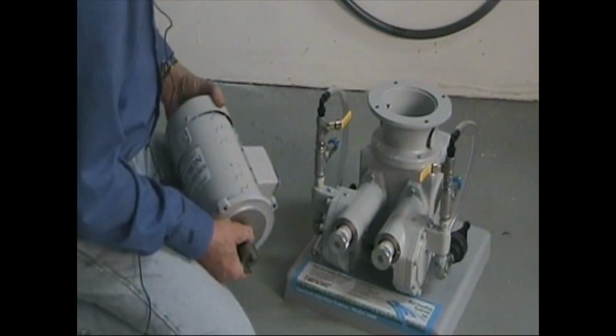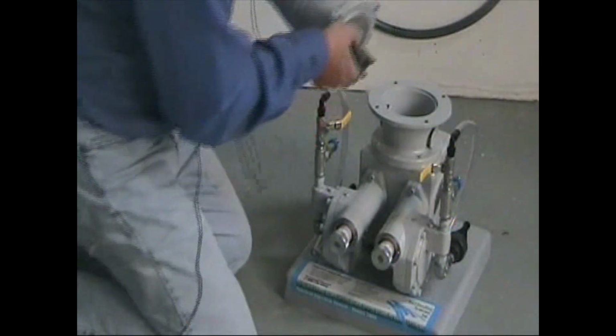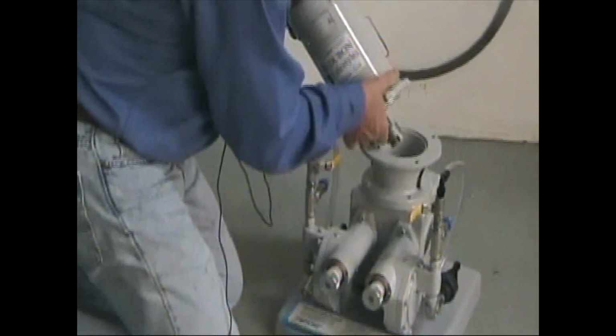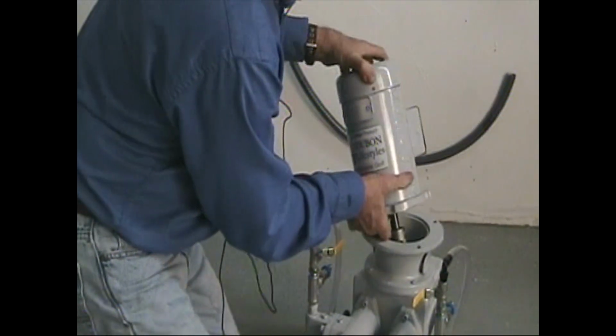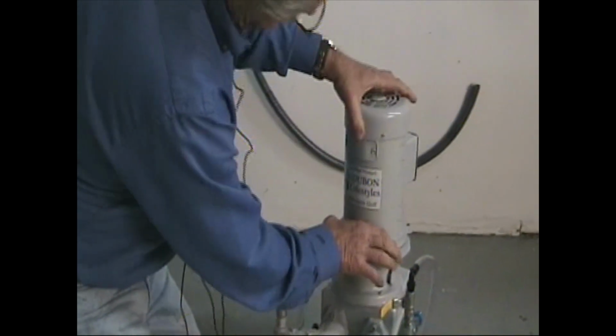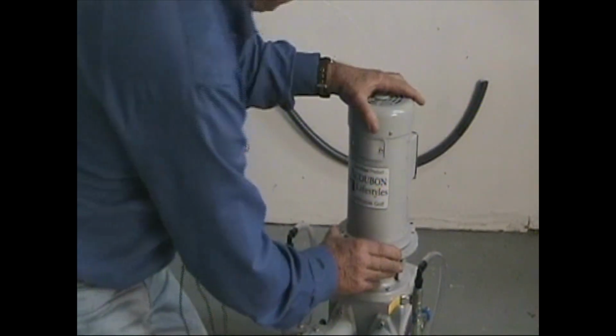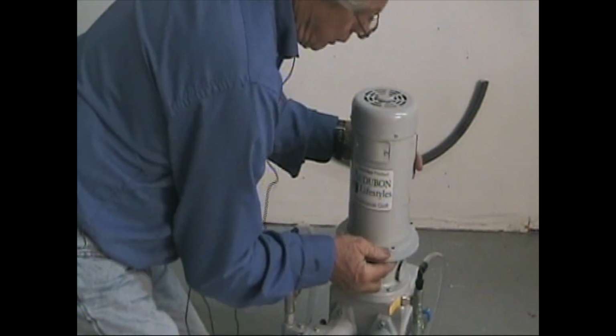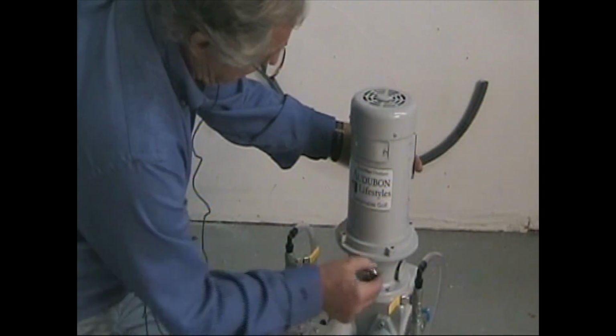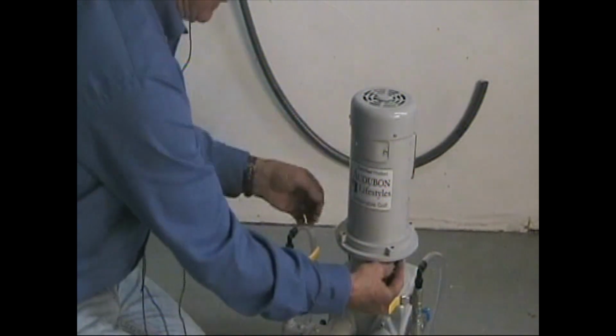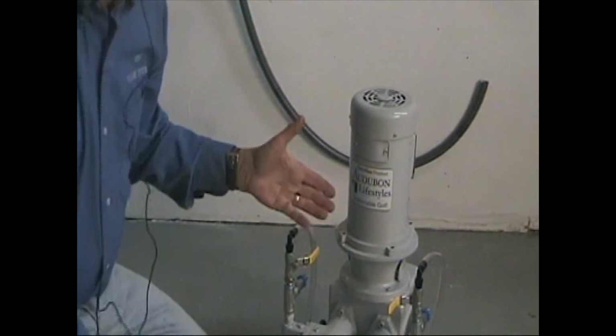Okay. The next thing you're going to do is mount the motor on the pump. The motor has a spider coupling that fits inside into special connections in the motor, shaft to shaft. Get your holes lined up, and you put your 4 bolts in and tighten them down, and you're all set.